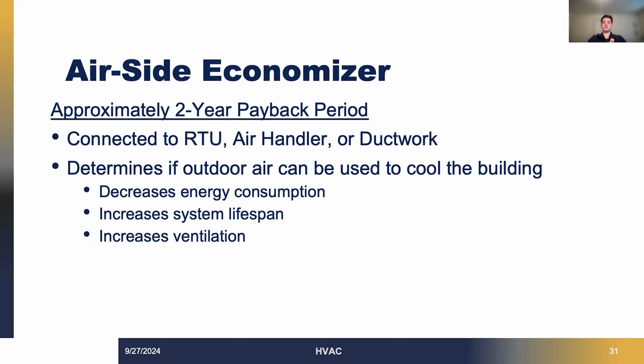Another effective strategy to enhance your system's energy efficiency is by implementing an airside economizer. These units are connected to rooftop units, air handlers, or ductwork, allowing outdoor air to be utilized for cooling the building instead of relying solely on conditioned air. Airside economizers are particularly beneficial during the fall and spring months, as well as in moderate climates where the outdoor air temperature closely aligns with the desired indoor temperature. By leveraging natural ventilation, these systems can significantly reduce energy consumption, lower operational costs, and improve overall comfort within the building. The payback period for an airside economizer is approximately 2 years, depending on the retrofitting needs of your company.